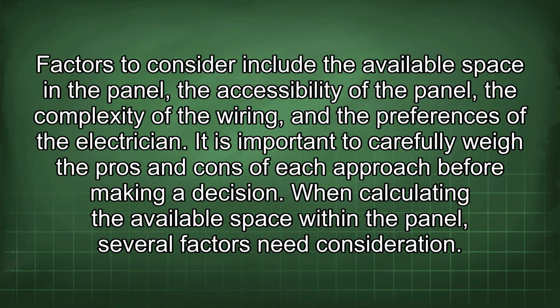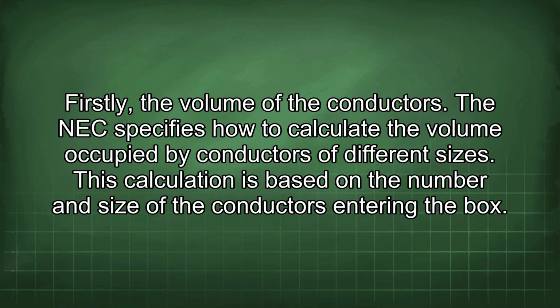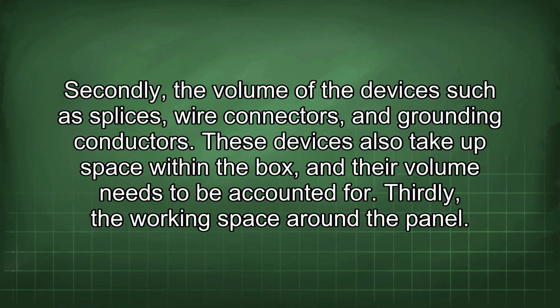When calculating the available space within the panel, several factors need consideration. Firstly, the volume of the conductors. The NEC specifies how to calculate the volume occupied by conductors of different sizes. This calculation is based on the number and size of the conductors entering the box. Secondly, the volume of the devices such as splices, wire connectors, and grounding conductors. These devices also take up space within the box, and their volume needs to be accounted for.